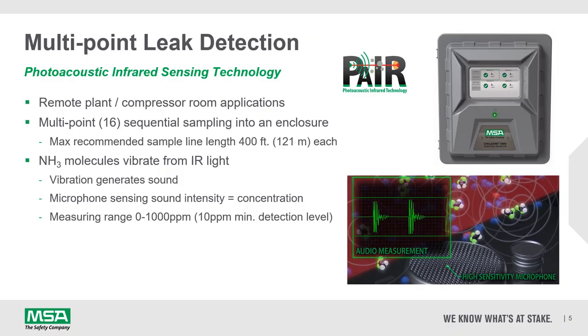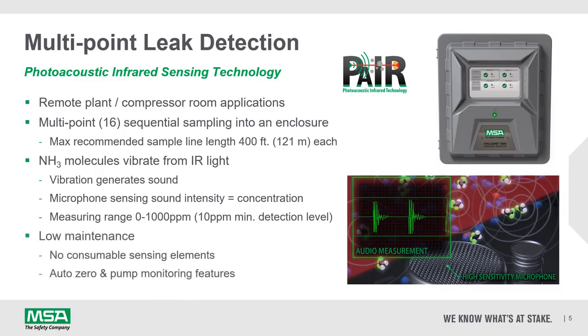This vibration in itself generates sound, which is then picked up by a high sensitivity microphone, and that is then converted to a gas concentration. This technology therefore enables measuring ranges of 0 to 1000 ppm with a 10 ppm minimum detectable alarm threshold. Such technology is also low in maintenance, as it has no consumable sensing elements, has an auto zero capability, and has self-diagnostics for monitoring the effectiveness and performance of pumps.